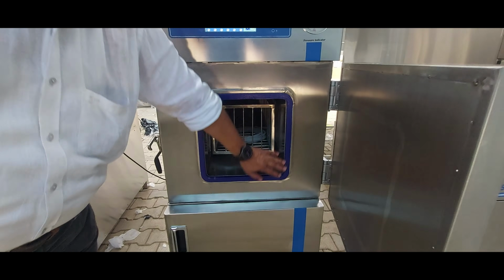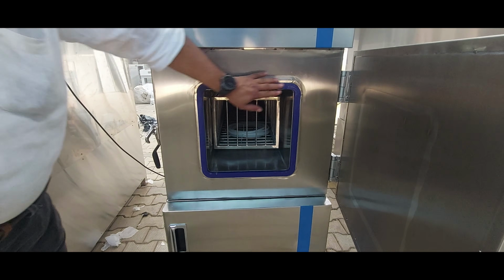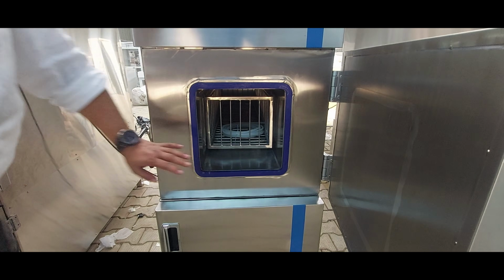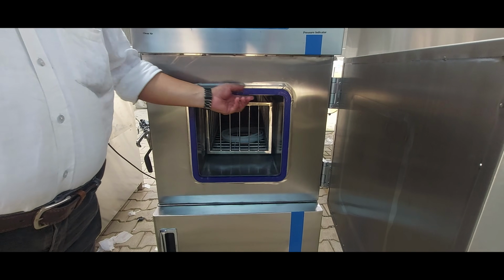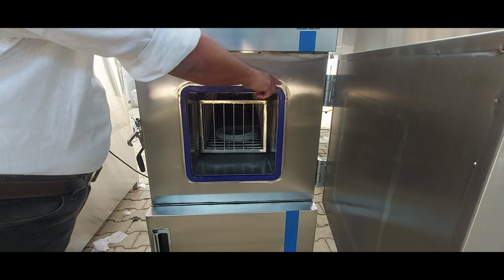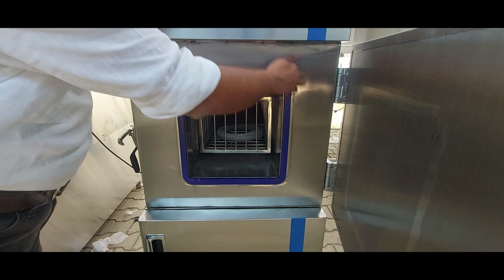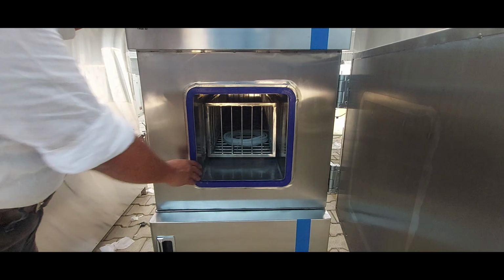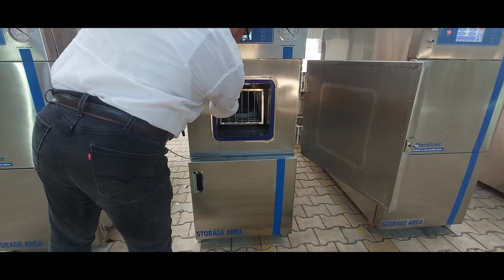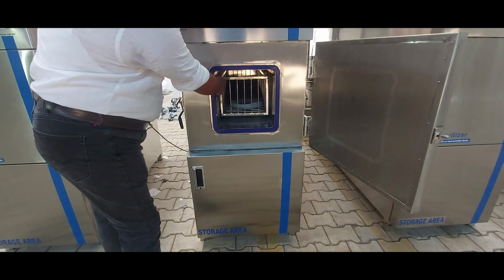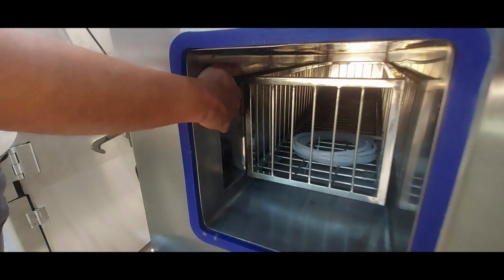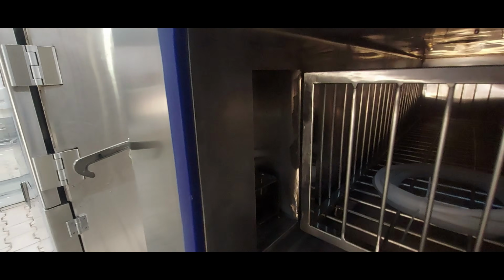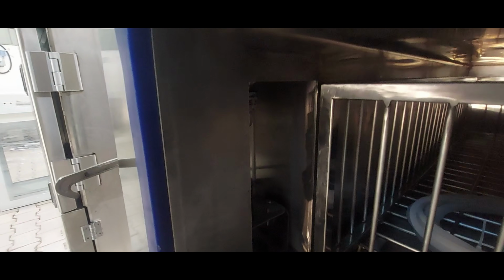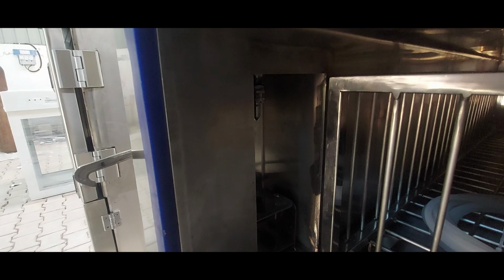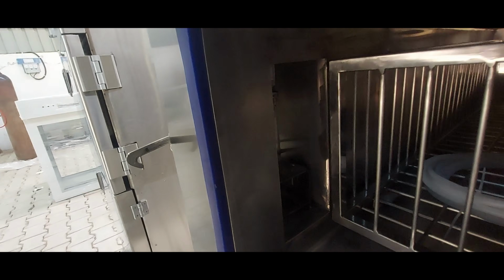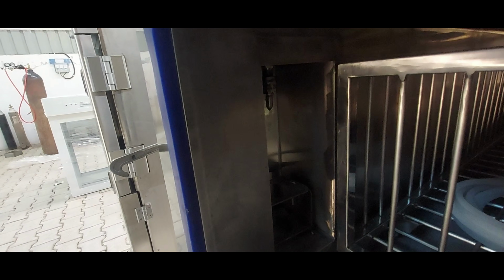Key design elements. Chamber design. ETO sterilizers utilize stainless steel chambers with features like single or double doors, depending on the customer's needs, and designs that support both positive and negative pressure. Control system. A sophisticated control system monitors and manages parameters like vacuum, humidity, exposure, aeration time, and temperature. Safety features. ETO sterilizers incorporate safety features such as leak tests, gas detection systems, and emergency evacuation systems to prevent gas leaks and ensure safe operation.